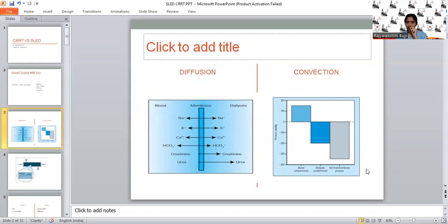So in contrast to diffusion, the removal of solutes doesn't depend upon concentration gradient, molecular size, or charge of the particle. The efficacy in terms of solute and solvent removal — that means removal of water, urea, creatinine, and whatever solutes we want to remove — compared to diffusion, convection plays a major role and is superior to the diffusion process.